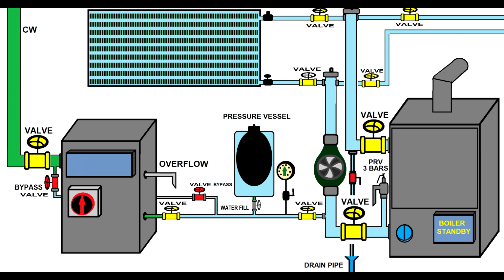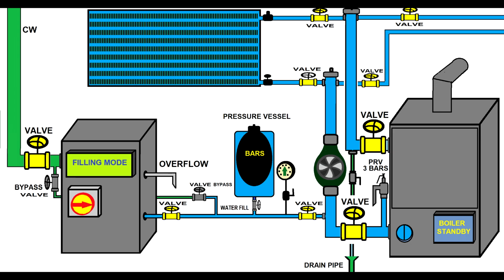Once your system is charged, you will turn off the bypass, and then you will turn on the pressurization unit, which will take over. You can program the pressurization unit, and in this case the pressurization unit will run until the water pressure reaches the set point. That will be a set point chosen by you according to your system design requirements. Don't rush to enable your boiler. First, run the pump. Allow the entire quantity of air to be eliminated.